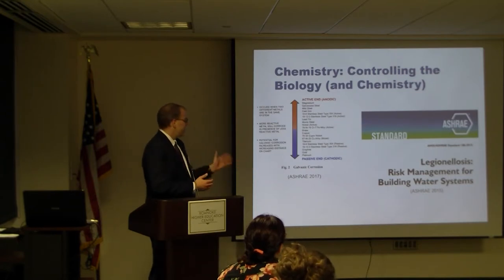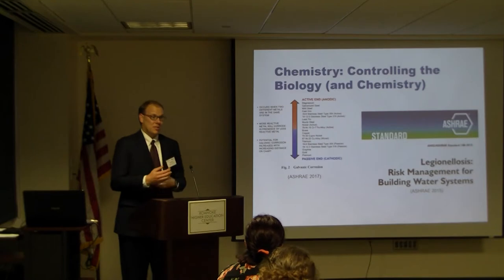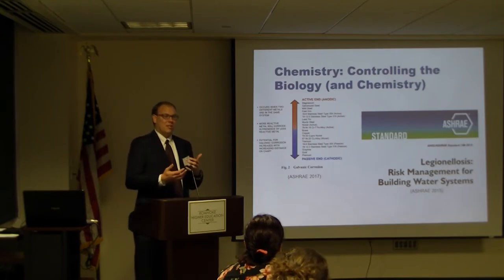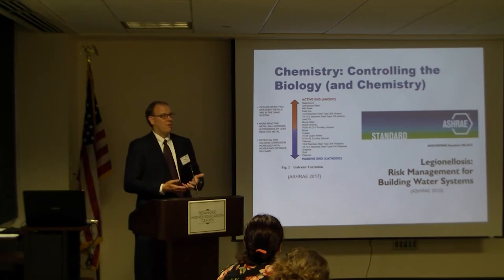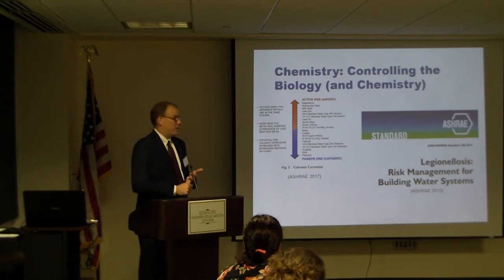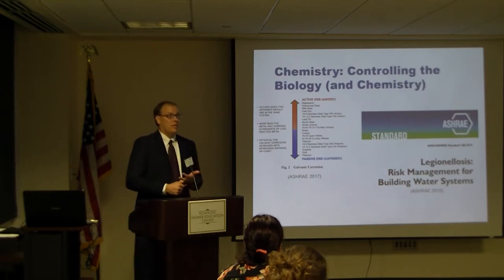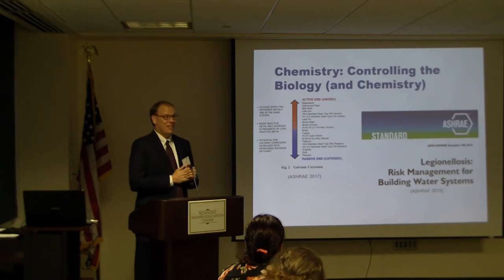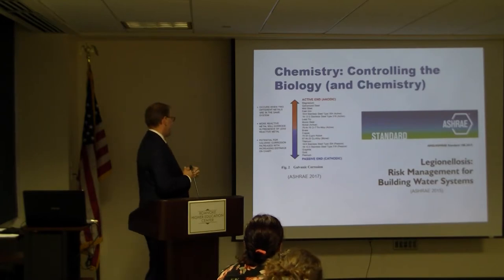The other thing we have to do from a water system is control the corrosion, the chemistry inside, the chemical makeup of our materials. We tend to use steel and copper inside of our systems. All the piping is either going to be likely black carbon steel or generic copper. Those two don't like each other. They're on slightly different ends of the cathodic galvanic scale.